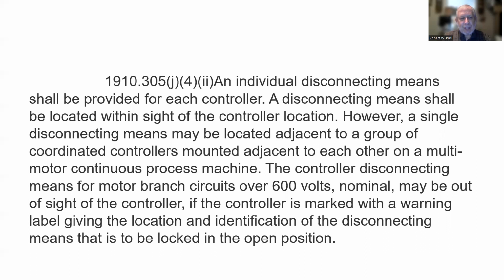However, a single disconnecting means may be located adjacent to a group of coordinated controllers mounted adjacent to each other on a multi-motor continuous processing machine. The controller disconnecting means for motor branch circuits over 600 volts nominal may be out of sight of the controller if the controller is marked with a warning label giving the location and identification of the disconnecting means that is to be locked in the open position. So there you go. They have a rule, and then the next paragraph, they break it.